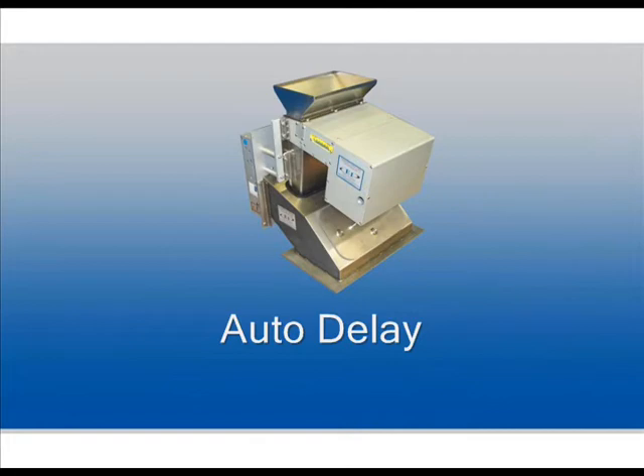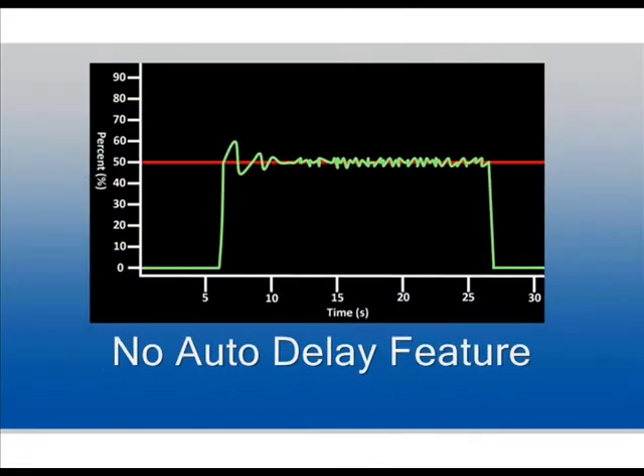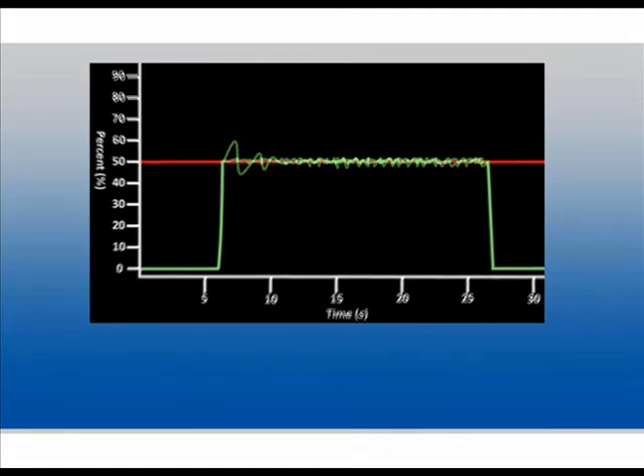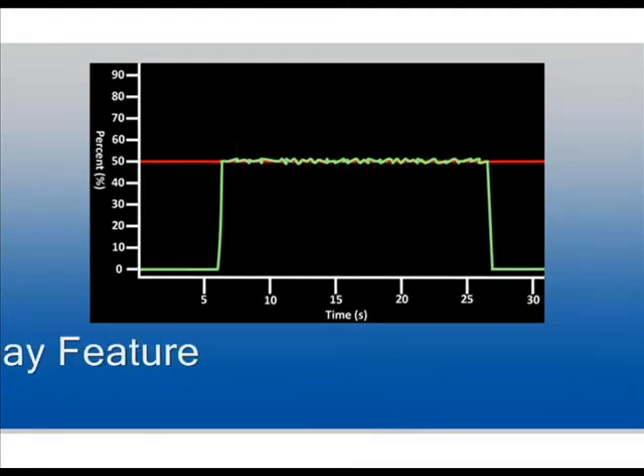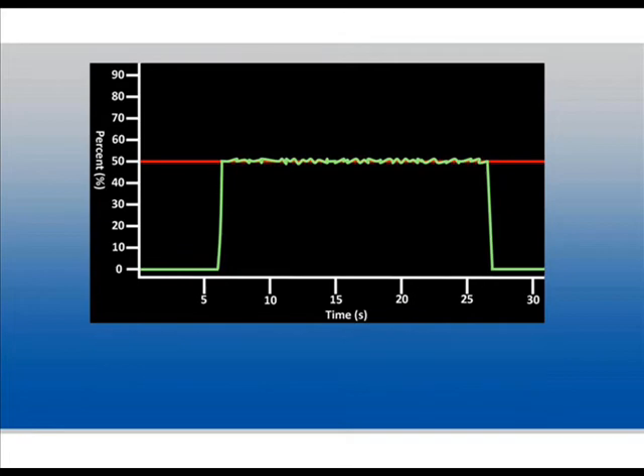To maintain consistent control even upon startup, the Centrifeder is equipped with auto-delay. This feature enables the Centrifeder to remember or retain an opening position for the valve, which correlates to the desired flow throughput. The retained auto-output value is held constant for a specified amount of time before entering automatic mode, which decreases the valve's tuning time and drastically reduces initial overshoot.